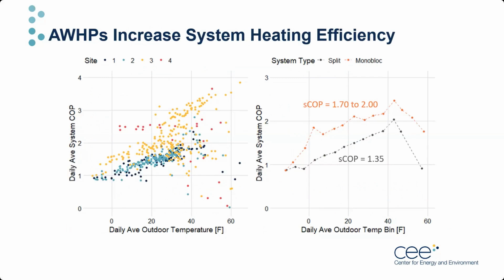So next, let's look at the achieved system COPs, averaged by day and displayed versus daily average ambient temperature on the x-axis. The plot on the left is the daily data, which is then further averaged into two clean profiles, one for the monoblock and one for the split system, displayed on the right. On average, the system COPs are a significant improvement over electric resistance or propane heating alone, which always have COPs of less than 1.